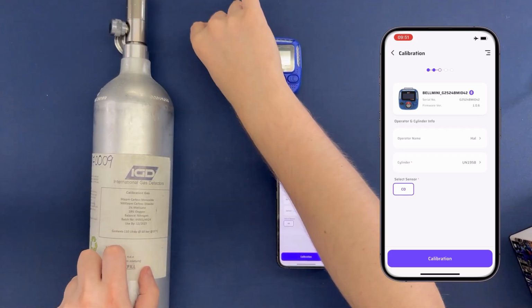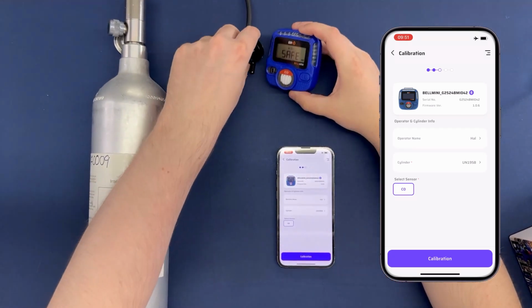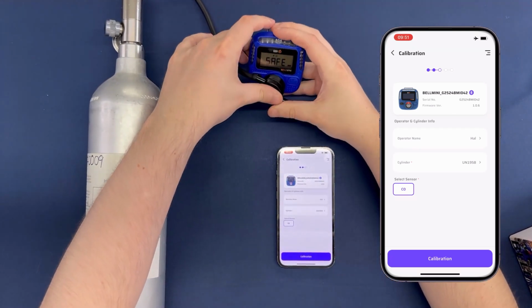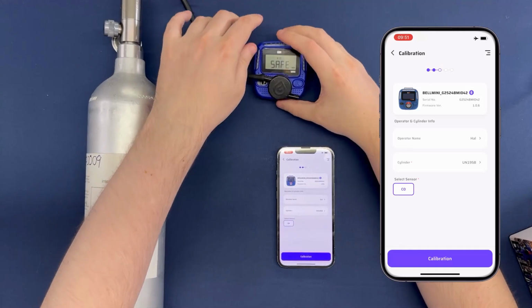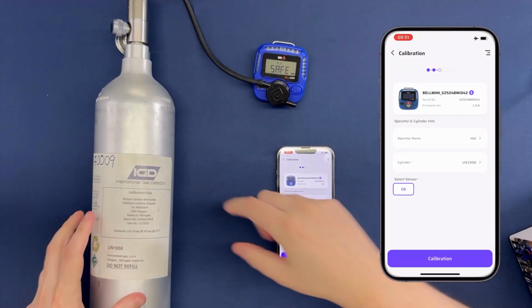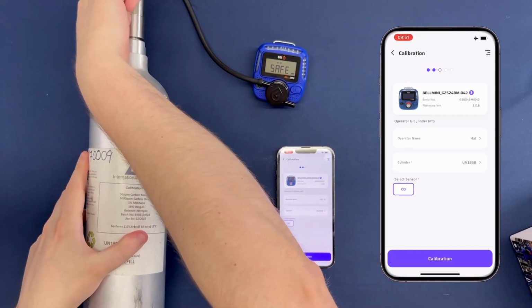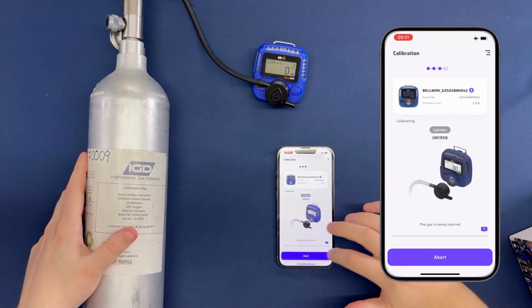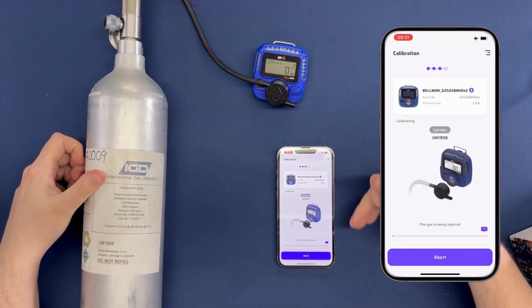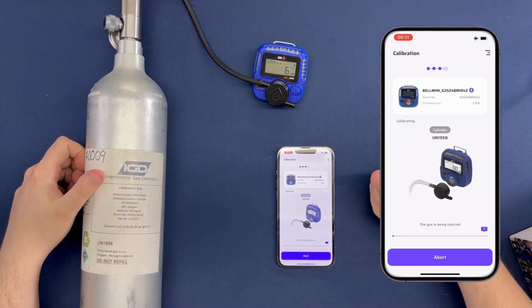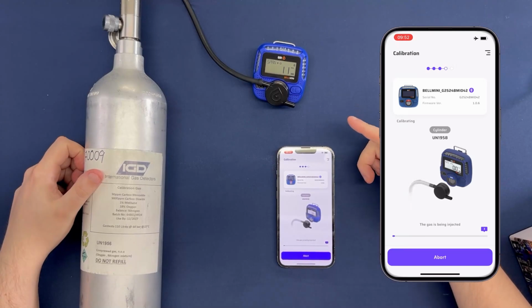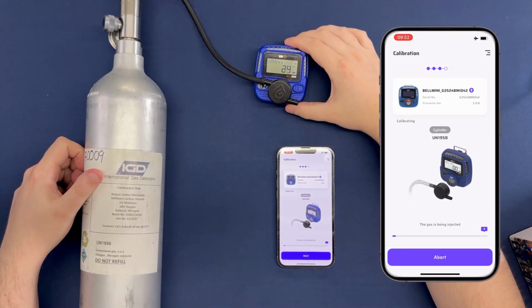And then at this point, I need to apply the calibration adapter to the sensor, and it just pushes on, as you can see. And then we turn on the regulator and press calibration. And as you can see, you have a little picture here that showcases what we've just done now, and the reading on the BELLMINI. As you can see the gas levels going up.